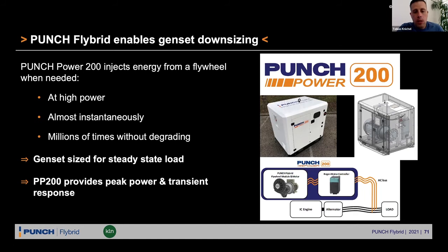As a result, the genset can be sized for the steady state load, so it can be optimized to run at a very narrow operating band. The flywheel then provides the peak power and transient load response. So you can have a primary power source optimized around a narrow band, and use the secondary flywheel energy storage system to deal with transients and peak power demands that only occur from time to time.